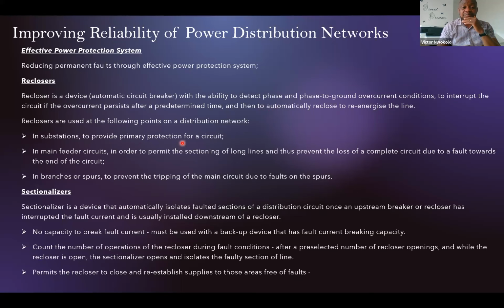If it continues and the fault persists and maybe the system assumes it's a permanent fault, a different device called a sectionalizer comes in. And what that does is, when the recloser is in the open state, the sectionalizer breaks the circuit. So you just keep that small section of the distribution network open until a field technician goes there. So when it does that, the recloser recloses again. And when it closes, the sections that are unaffected by the fault will still remain with power, while the small section the sectionalizer cut off is the one that will remain for field technicians to look at.